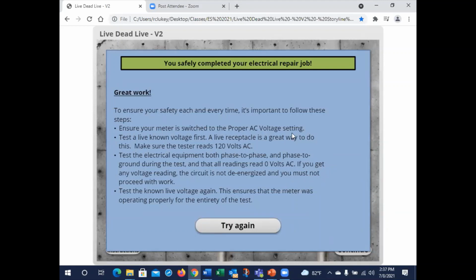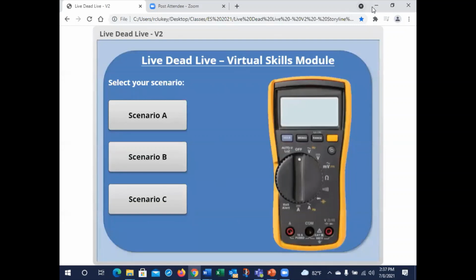I can remember starting in the trade in the early 70s, and my supervisor told me, test before you touch. That's about all he ever said. Gave me a little meter and said, if this thing illuminates, don't touch it. We've come a long way since then, right? We now are guaranteeing that our meter is going to work properly. We are going to test phase to phase and phase to ground, make sure it works properly after we do all that, and then we can go ahead and do our repair on that equipment.